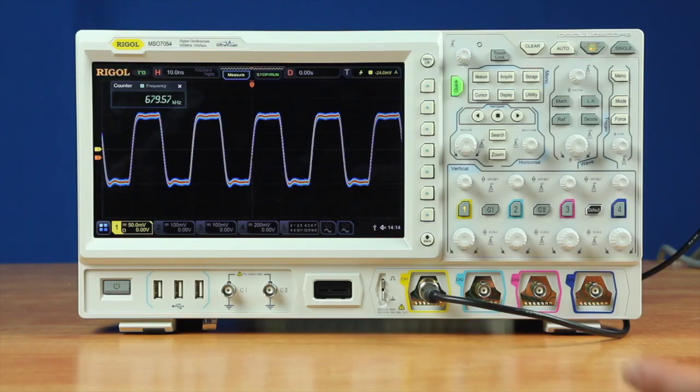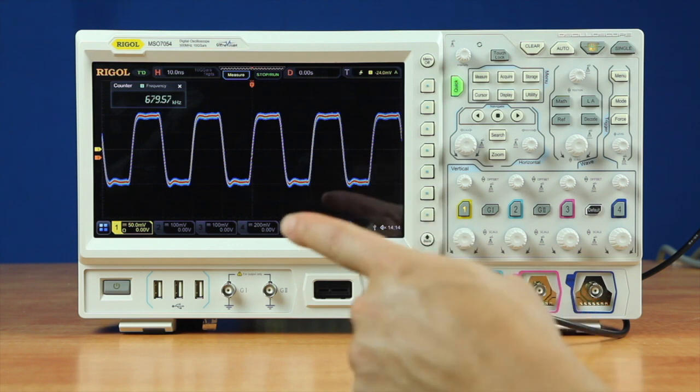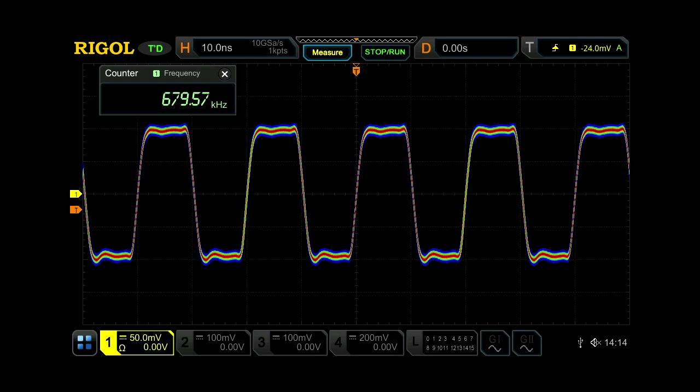On the Rigol, with the same settings and signal, we've also added a frequency counter to capture directly the waveforms per second rate from the trigger out and the external trigger input. So with that frequency counter on, we can see we're measuring about 680,000 waveforms per second to start with.